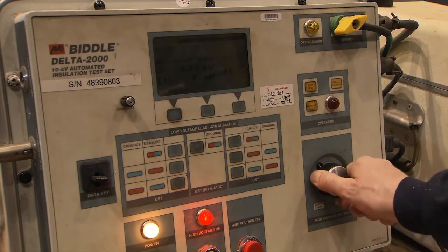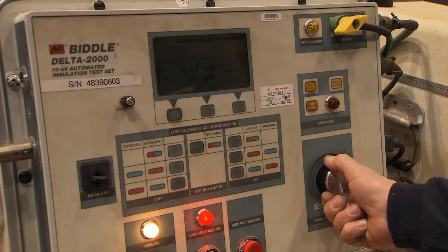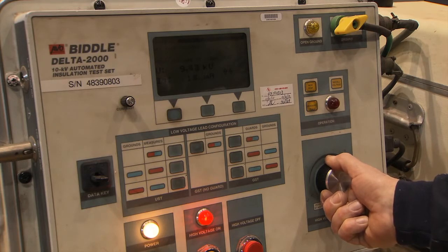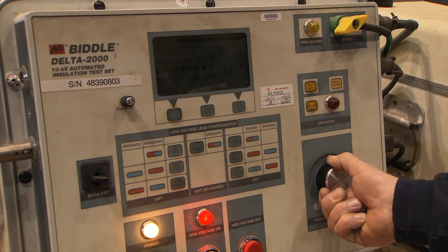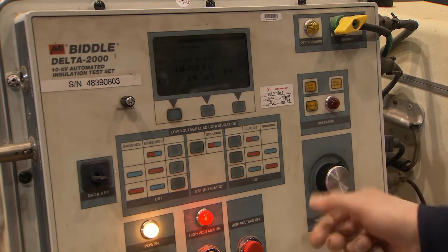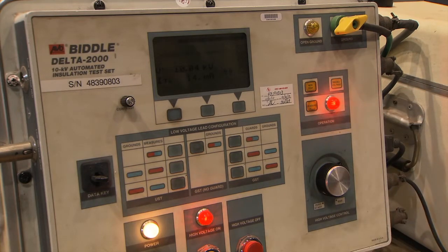Rotate high voltage control knob to set point of 10 kilovolts, indicated in the digital display window. And then press the Measure button on the operation panel. The test is complete when a set of results appears in the display window and the red operation light goes out, followed by the red high voltage light, indicating that the high voltage switch has shut off.